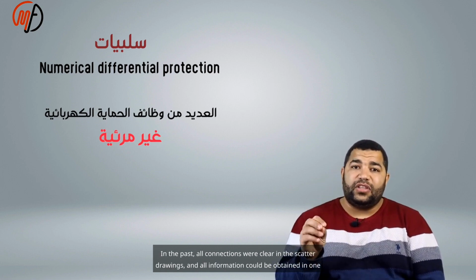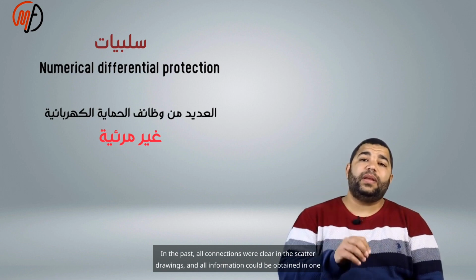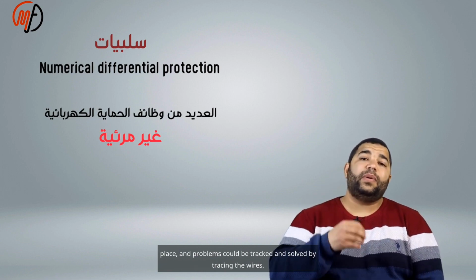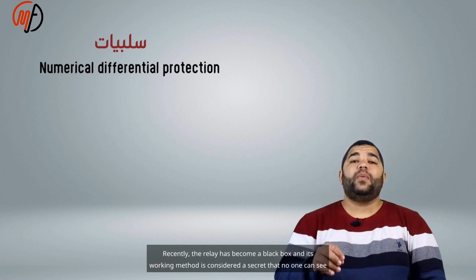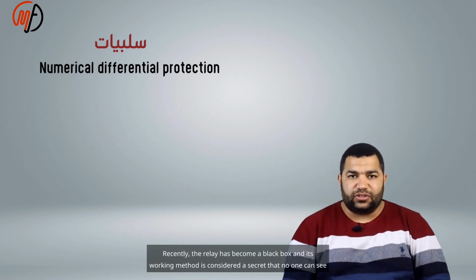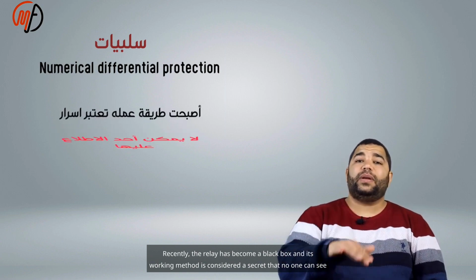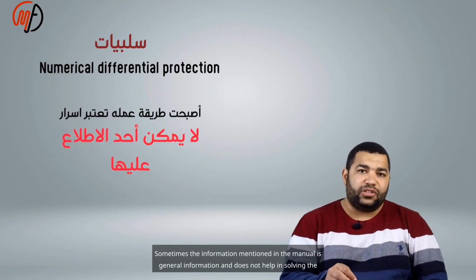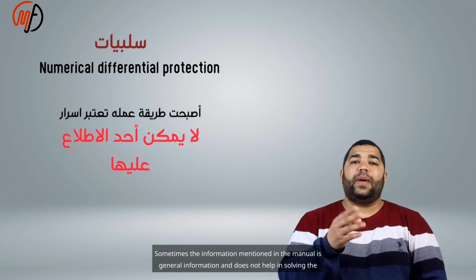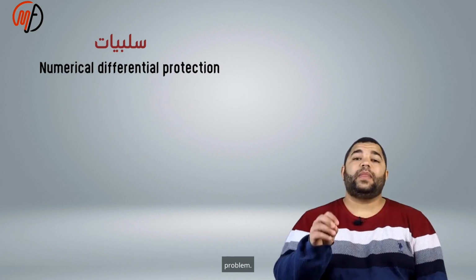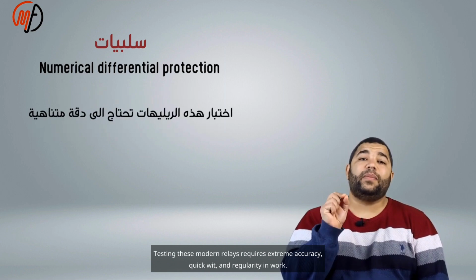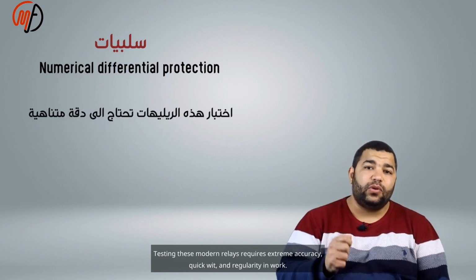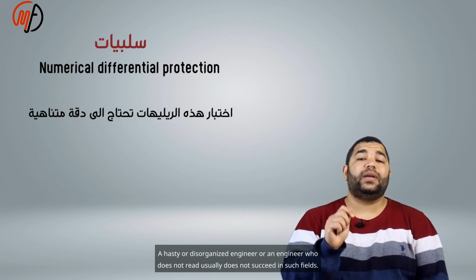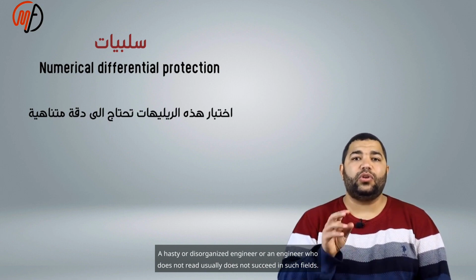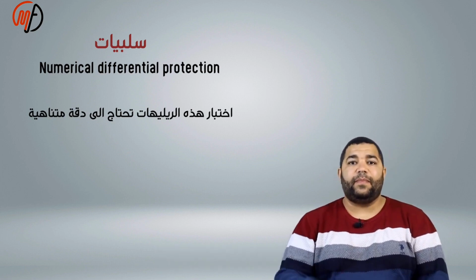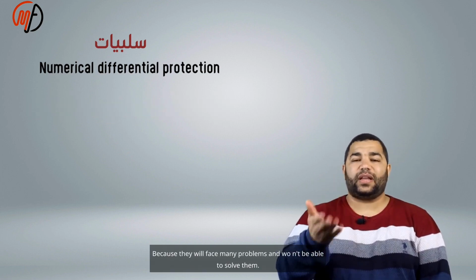In the past, all connections were clear in the scatter drawings, and all information could be obtained in one place, and problems could be tracked and solved by tracing the wires. Recently, the relay has become a black box, and its working method is considered a secret that no one can see. Sometimes the information mentioned in the manual is general information and does not help in solving the problem. Testing these modern relays requires extreme accuracy, quick wit, and regularity in work. A hasty or disorganized engineer, or an engineer who does not read, usually does not succeed in such fields, because they will face many problems and won't be able to solve them.